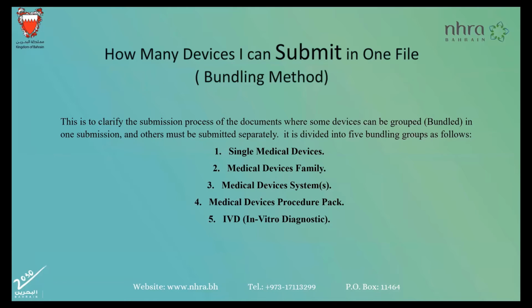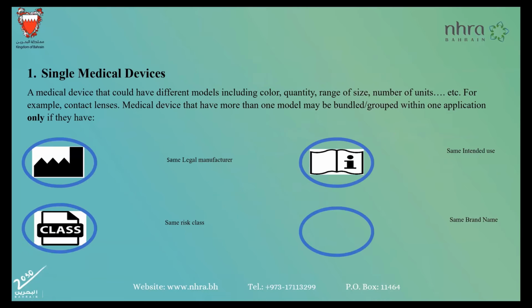Bundling methods. To submit more than one device in one application, it is divided into 5 categories. It has to be from these 5 groups: 1, single medical device; 2, medical device family; 3, medical device system; 4, medical device procedure pack; 5, IVD. For a single medical device, they can have different models, different colors, different sizes. It doesn't matter, but they have to be from the same legal manufacturer, with the same intended use, same risk class, and same brand name.